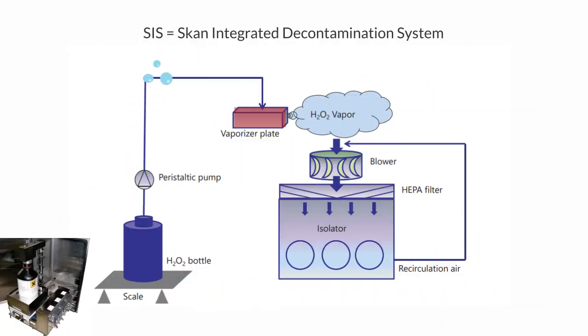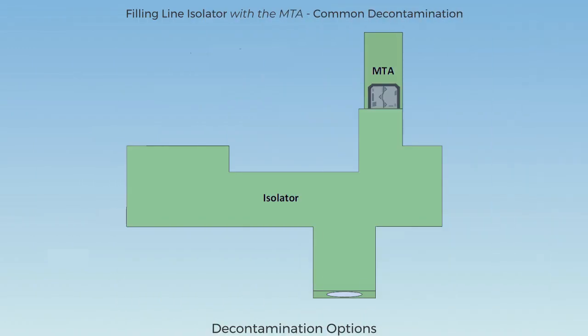The isolator is equipped with a decontamination system designed to provide decontamination of the isolator and filling machine parts enclosed within the isolator chamber with hydrogen peroxide, H2O2. The first decontamination option is the filling line isolator with the MTA. After start of the common decontamination cycle, a combined leak test will be performed. The transfer door is open, and the filling line isolator starts with the decontamination cycle.